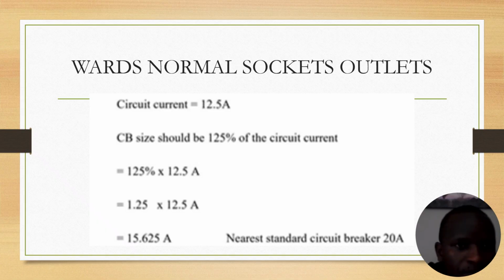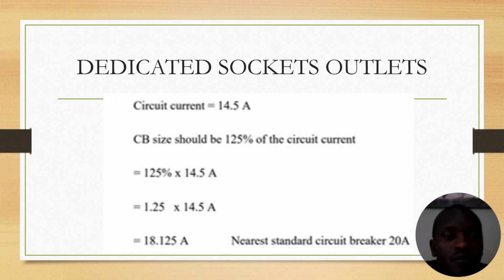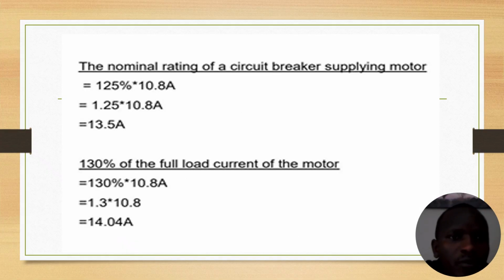For the wards normal socket outlets, it will be 15.625 amps. The nearest standard will be 20 amps. So there is the standard. For the dedicated socket outlets, it's also 18.125, where the nearest standard will be 20 amps. The nominal rating of a circuit breaker supplying the motor will be 13.5 amps. Then we are going to multiply it by 130%, which will give us 14.04 amps.